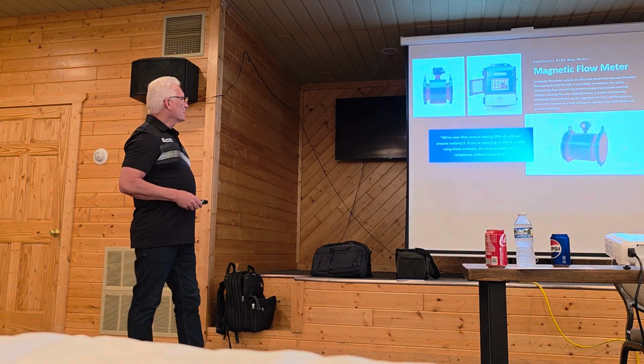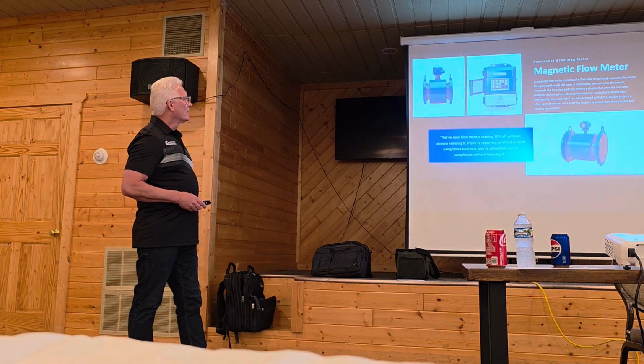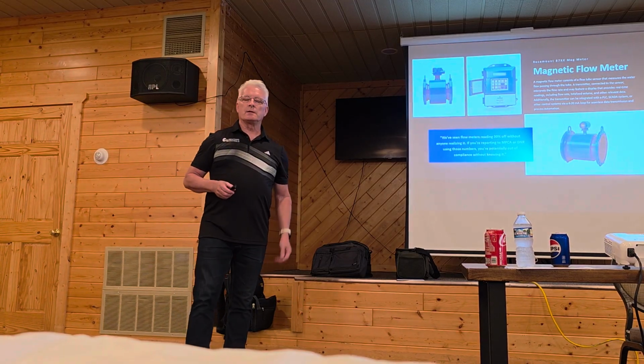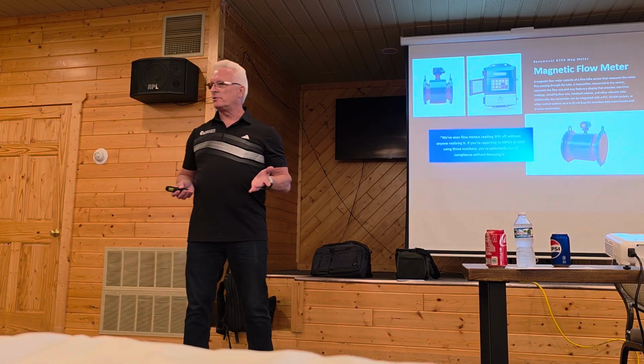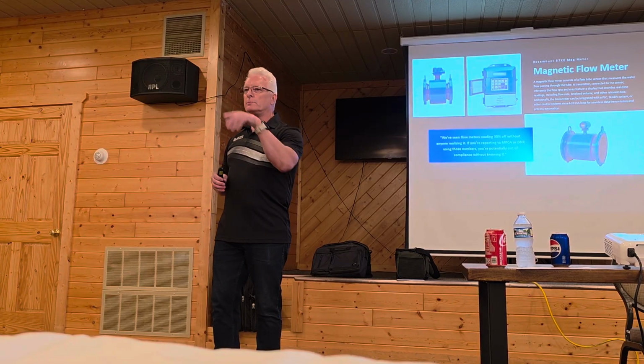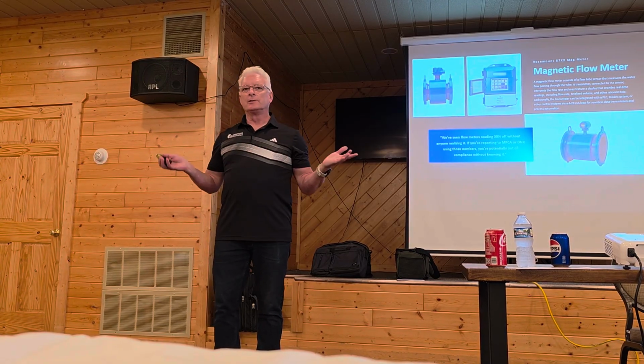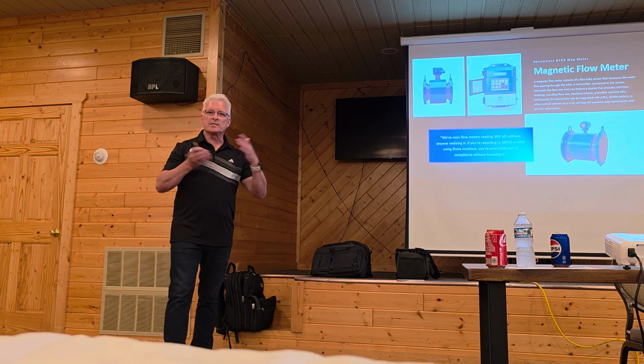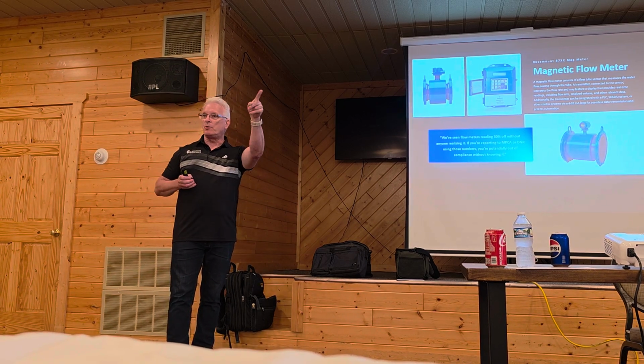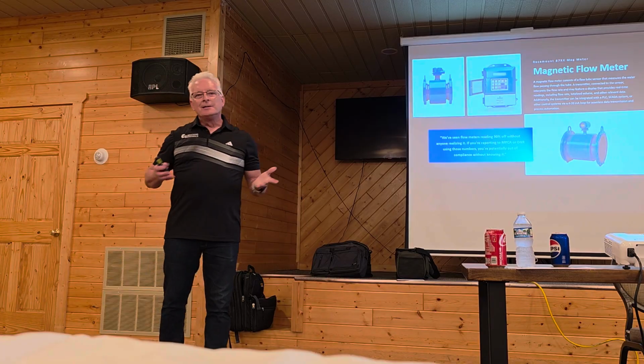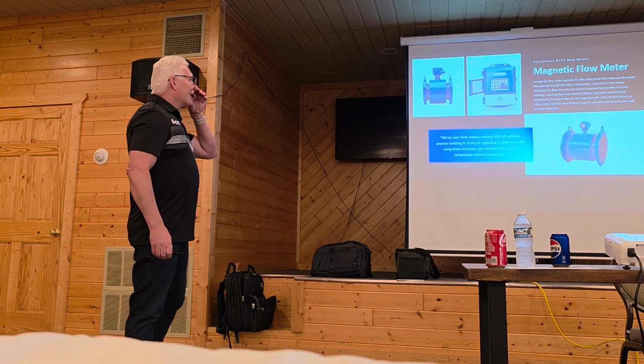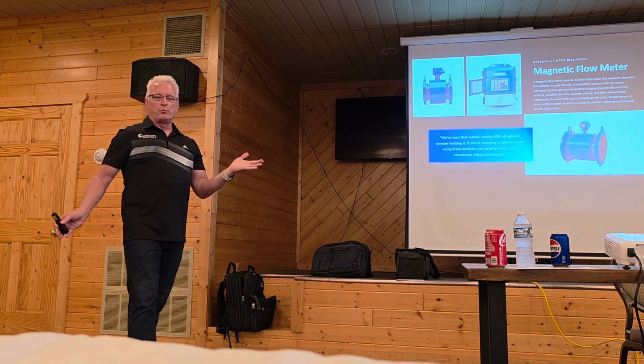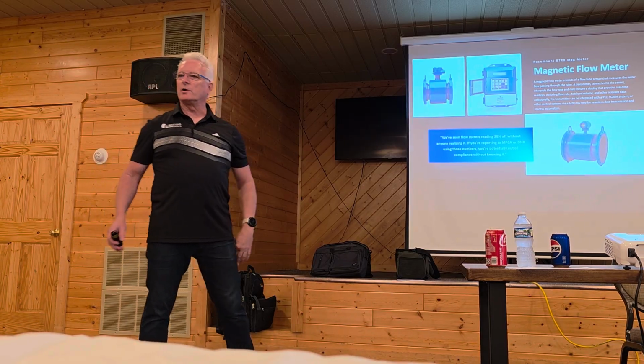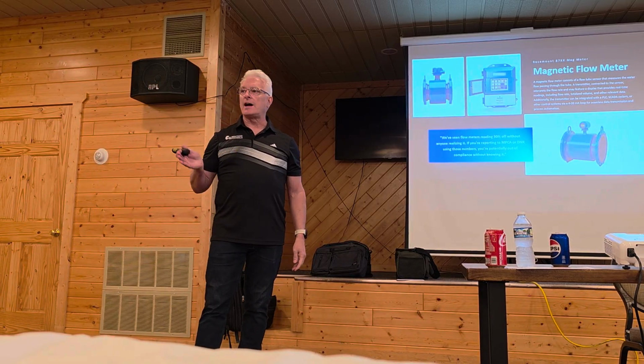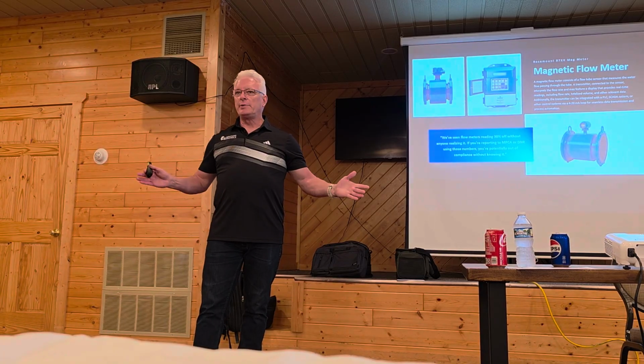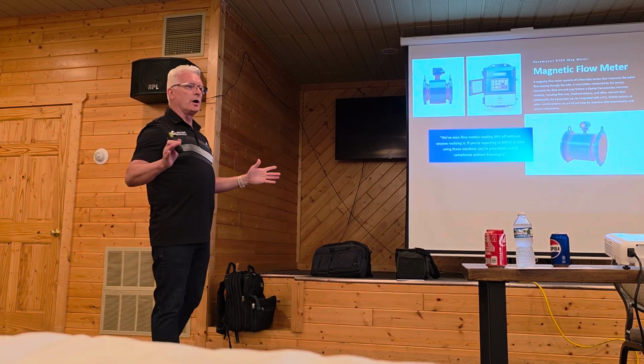Magnetic flow meters are about 0.5% accuracy in our industry, almost all of them. They'll say 0.4, some will say 0.5, some will say 0.6. Everybody's trying to sell something, so they say it's a little bit better because they saw it one time it was like this. But they're all basically 0.5%, and that's normally what's efficient in water and wastewater. The old propeller meters are 2.5 to 5%. So that's a big difference in your water.